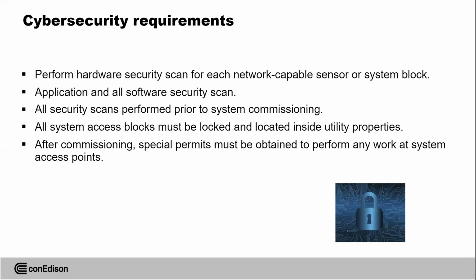We don't like two-way communication, so all ports we will not use should be closed. All system access blocks must be locked and located inside utility properties. We install them in substations, and after we do the final cybersecurity scan, no one can touch that server. And special permits must be obtained to perform any work, updates, patches, or whatever we do for the system to keep it alive.